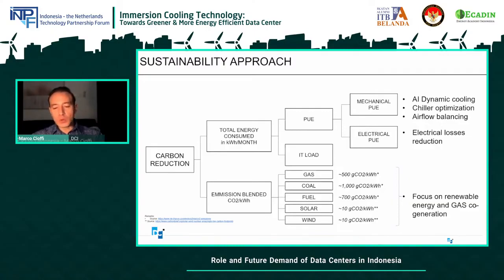So what we can do as a data center sector is look at mechanical and electrical PUE. The largest driver of PUE is mechanical PUE. This is intuitive—think about your home. Electricity losses from a server to the plug are basically just cable, so cable losses are limited. But think about how much electricity we need to run our air conditioning: fans have to move, compressors have to work, liquid has to move from A to B. So mechanical PUE is very important.